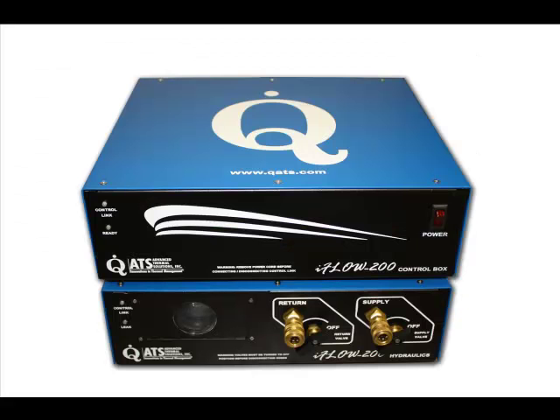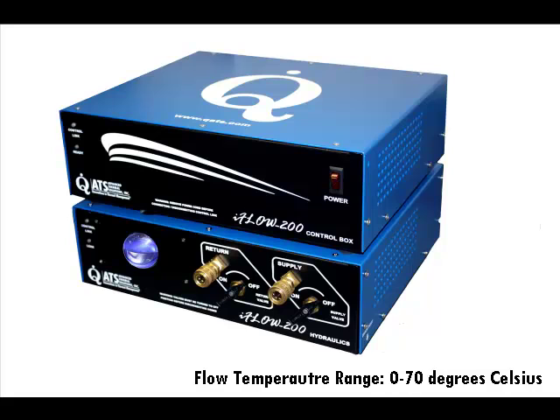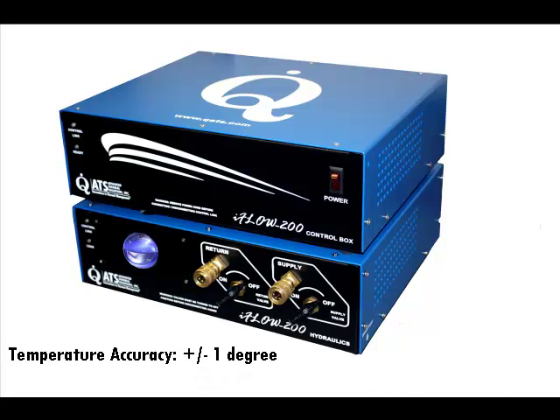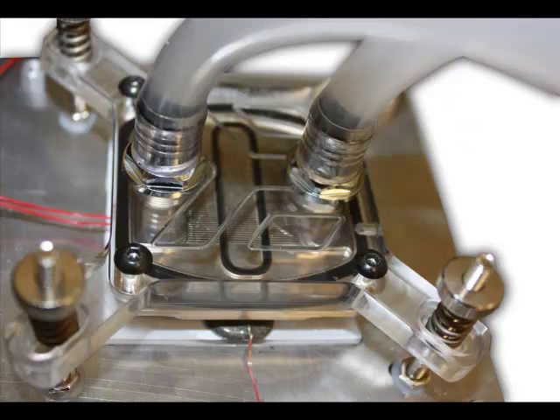It replaces the complex process of varying the volumetric flow rate of the coolant and measuring the pressure drop and temperature of the cold plate. The iFLOW-200 measures coolant temperatures from 0 to 70 degrees Celsius with a high accuracy of plus or minus 1 degree Celsius. The differential pressure of the coolant in the cold plate is measured up to 103,000 pascals or 15 psi with the precise accuracy of plus or minus 1%. Distilled water is used as the reference coolant.